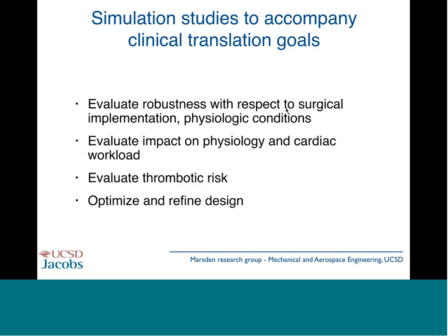It's very important to not only optimize the design for a particular geometry, but knowing that the surgeon is likely not going to implant exactly the geometry that we intended, we want to make sure that slight deviations from that geometry would not adversely affect the results.